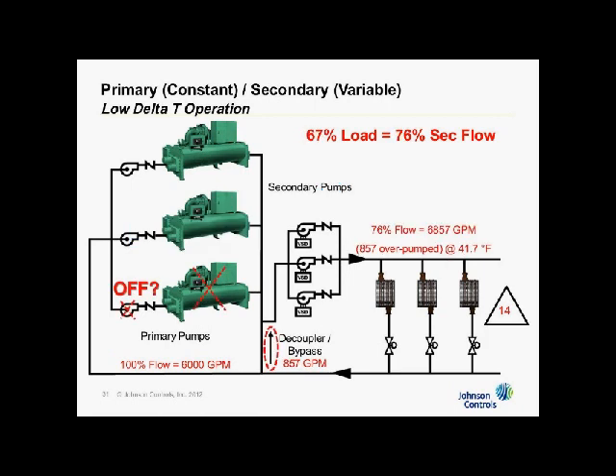Let's take another look. Let's go to 67% load and see what happens, because there's two things that happen here. One is that I have to overflow again, 76, which means I'm over pumping to 857. My 6,000 GPM that's over in my primary, because this one is off, I'm going to turn it off. I'm going to just shut it off because 2/3 capacity is what I have. So 2/3 capacity is what I need in terms of load. But I need more flow. I need 857 more flow. So what happens is when I shut this pump off here and this chiller off and isolate it, I've got 6,000 GPM in my primary. I've got 8857 in my secondary. So the last 857 has to go backwards through the common.